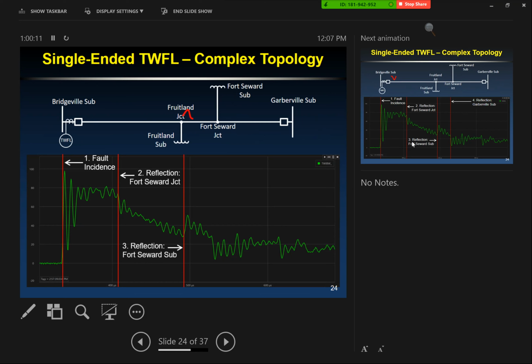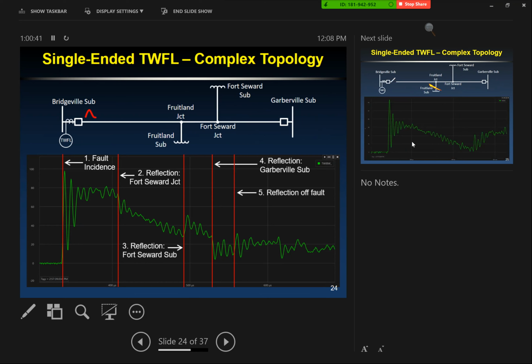And you get a reflection off Garberville. Garberville was closed because this happened when the line was just energized sitting there, and so you get a clean reflection back and it's negative. So what about the actual fault location, right? It's nice to map out these other points and reference them, but where is it actually bouncing off the fault? Fault going back to Bridgeville, back off the fault, back to Bridgeville sub. And that's this point here. This is our fault location we're interested in.